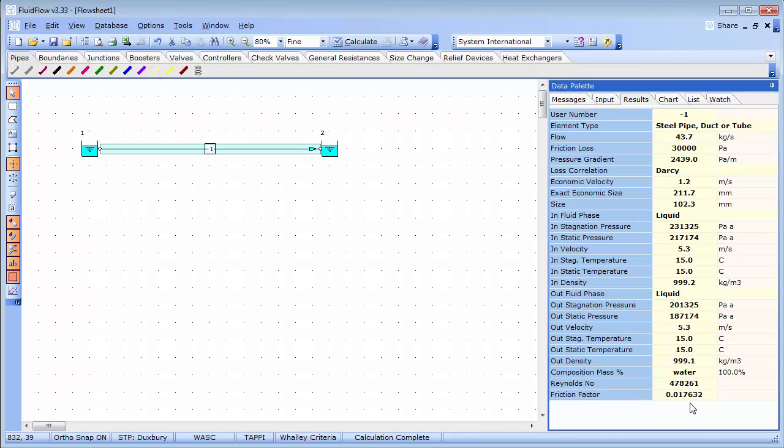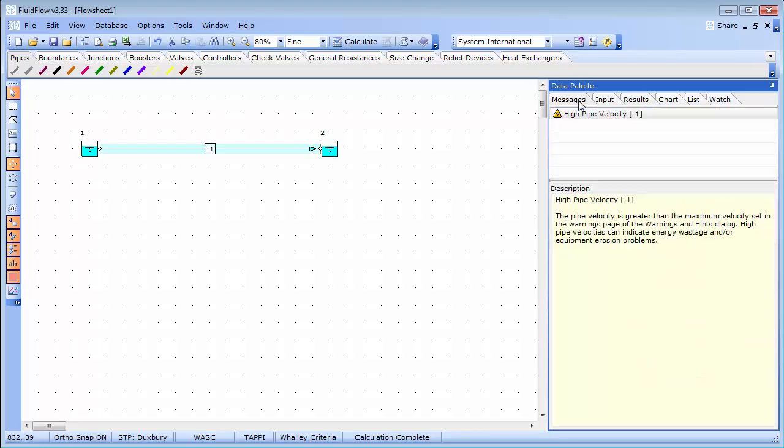Fluid flow automatically creates warnings which can be viewed on the messages tab. Warnings are enunciated to help users develop efficient designs. In this case, we have a high pipe velocity warning for pipe node minus 1. If we select the warning, a description of the message appears below.